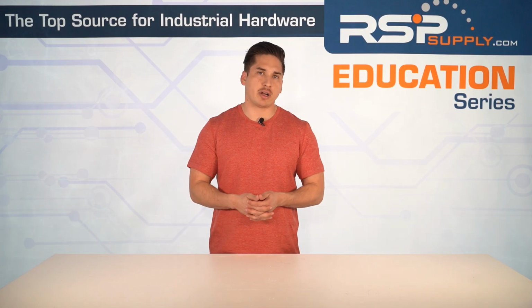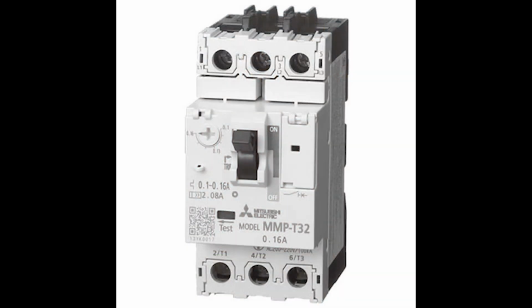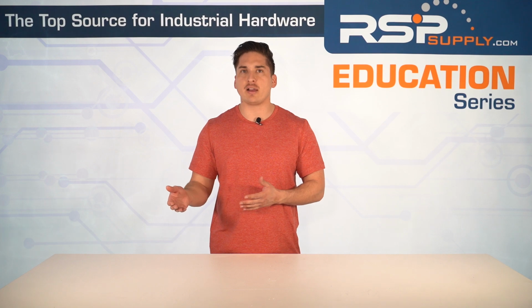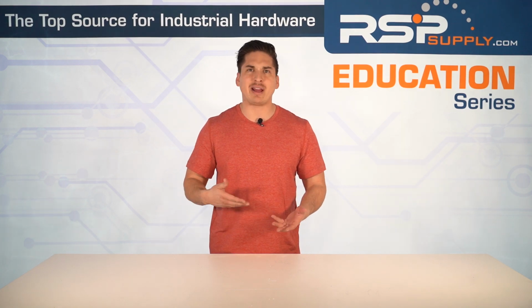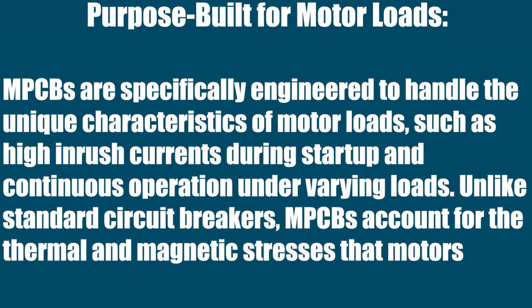So, motor protection circuit breakers. In industrial automation, MPCBs are specialized devices that are designed to safeguard electric motors, which are critical components in many industrial processes. Here's a breakdown of their functionality and importance at a mid-range level. Purpose-built for motor loads. MPCBs are specifically engineered to handle the unique characteristics of motor loads, like high inrush currents during startup and continuous operation under varying loads. Unlike standard circuit breakers, MPCBs account for the thermal and magnetic stresses that motors experience.